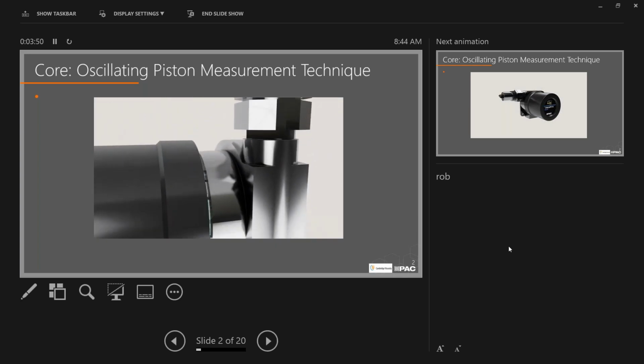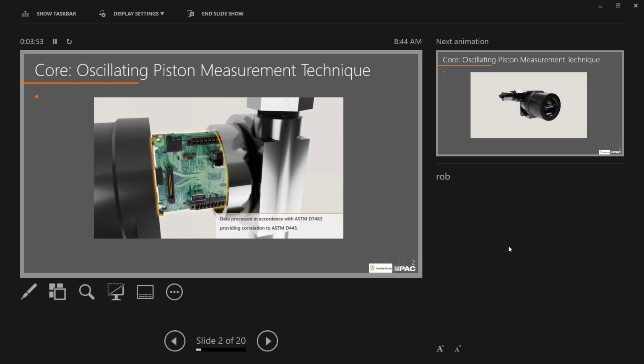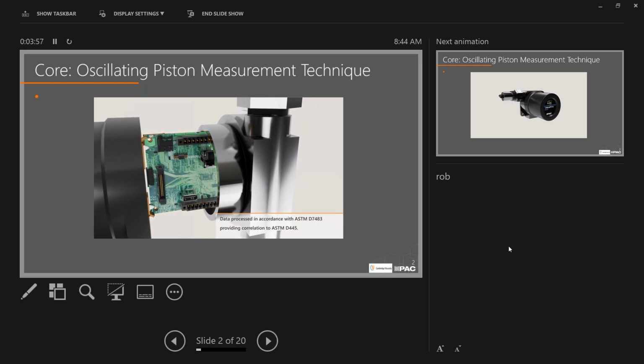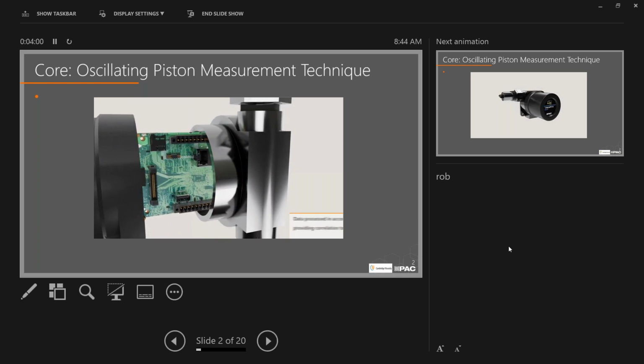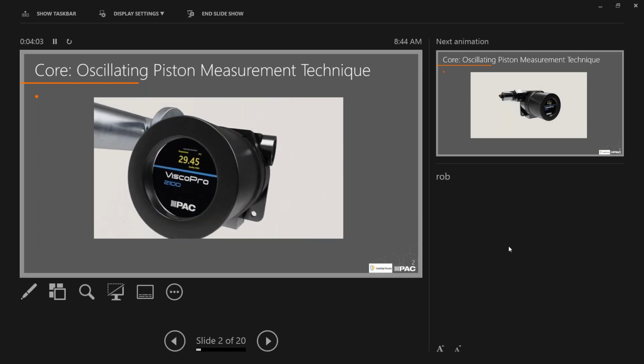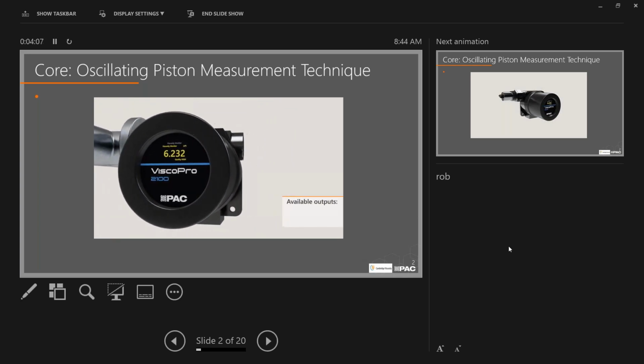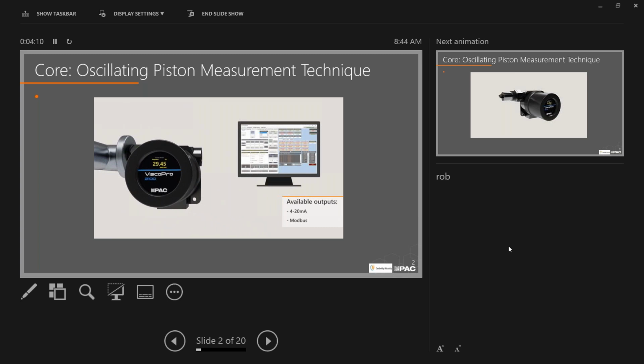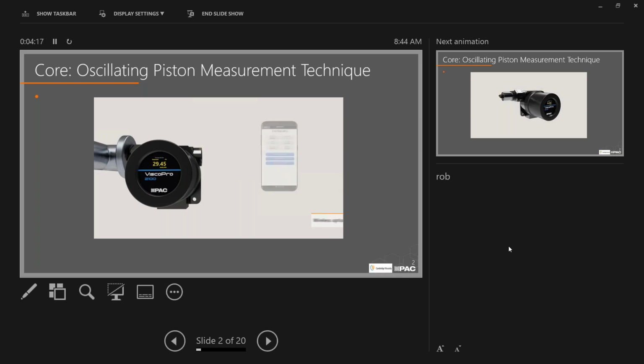Data from the sensor is processed in the electronics in accordance with ASTM D7483, providing correlation to ASTM D445. Measured data is displayed directly on the analyzer. Outputs are available in 4 to 20 milliamps and Modbus to allow customers access to information where they need it most. The user interface can be either hardwired or accessed on a smartphone via the wireless option. The UI allows for changes in settings, units, and calibrations, as well as downloading of the error log and data log. For more information about our viscosity measurement solutions, visit www.cambridgeviscosity.com.